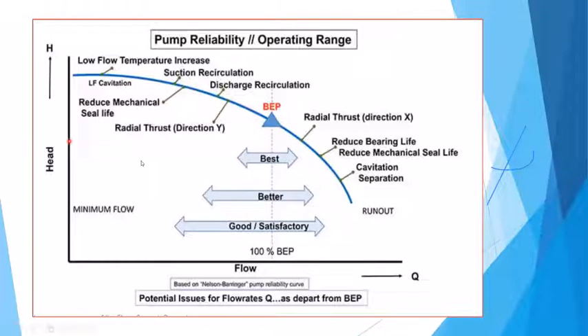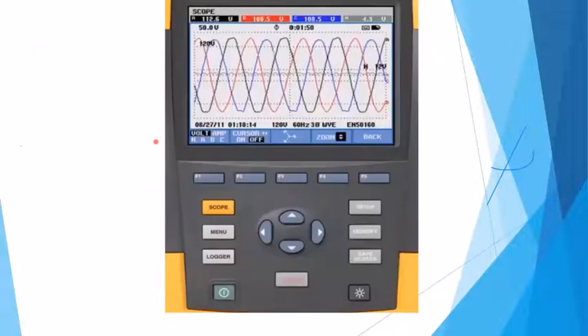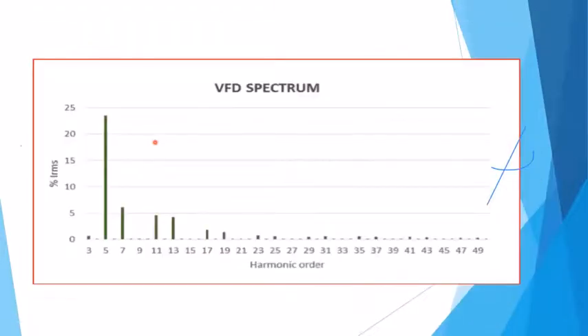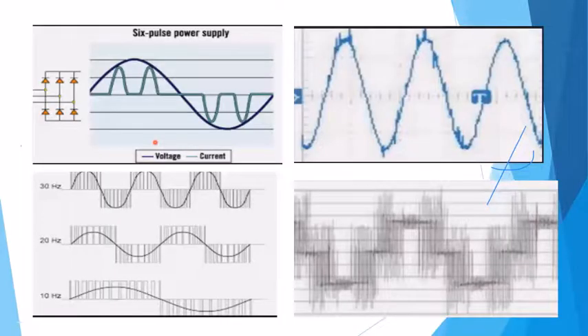Also, I've got a question. It says, hi, please tell about the insulation between the coils and coil to coil of a VFD motor. So the question there is, as we're doing this PWM coming out of the VFD, this is the waveform. You'll see these higher spikes. This is like peak to peak voltages here. It ends up jumping, and you'll see it on the scope here, these instantaneous little spikes.